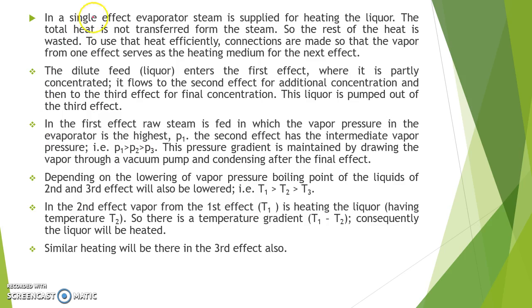In a single effect evaporator, steam is supplied for heating the liquor but the total heat is not transferred from the steam, so the rest of the heat is wasted. To use that heat efficiently, connections are made so that vapor from one effect serves as the heating medium for the next effect.